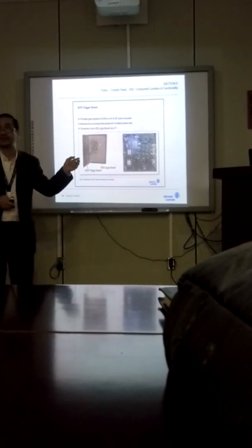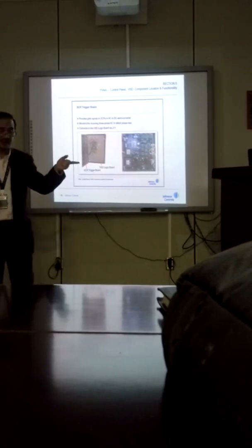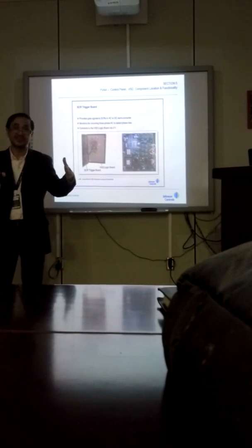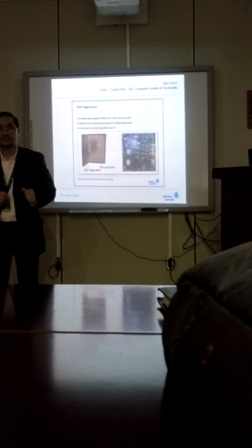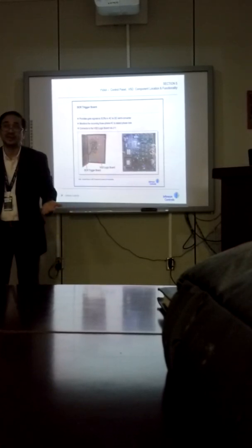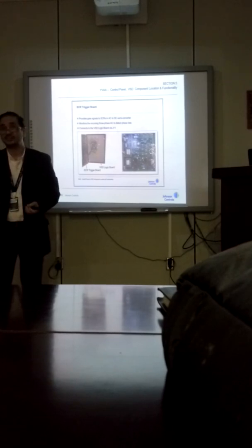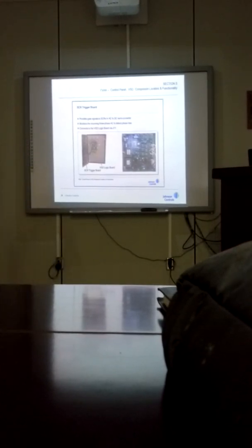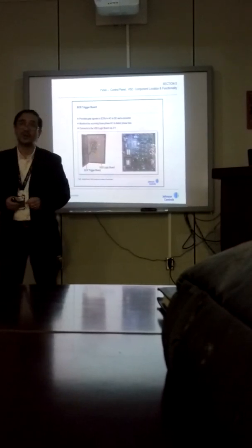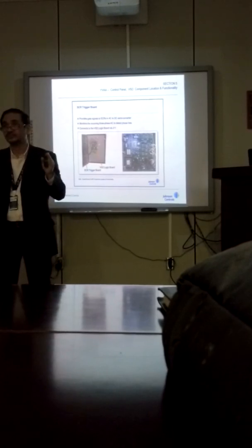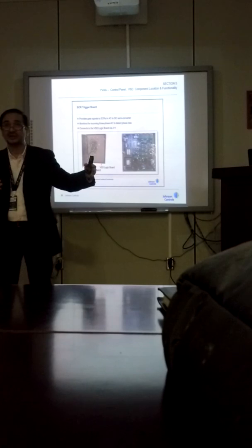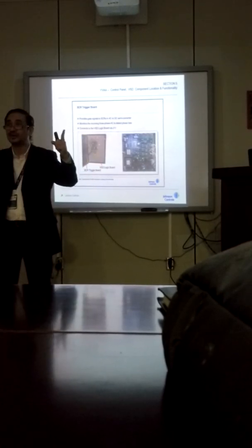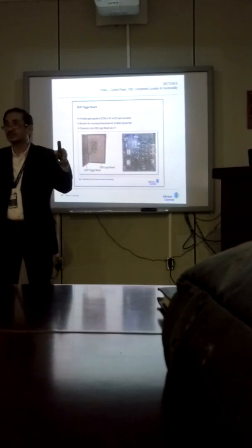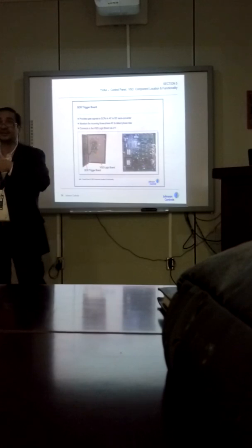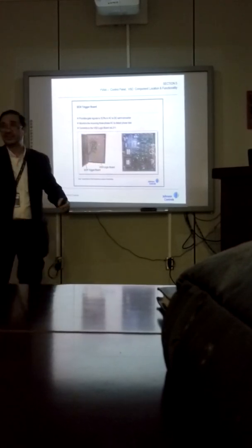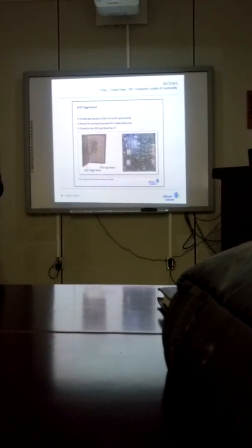Now your machine is 380 volts, correct? If it is 380 volts, I expect your DC at the VSD would be 537. How do I get that? Do I just guess it? No, sir. From an electrical point of view, you multiply square root of 2 to 380. Remember, why square root of 2? Because you have only 2 outputs. Your input is line 1, line 2, line 3, correct? But your output is DC. You have 2 outputs only, 2 wires. So the output of that, multiplied by square root of 2, your input is 380. So the output is DC. So 380 multiplied by square root of 2, 1.414, will be 537 volt DC.